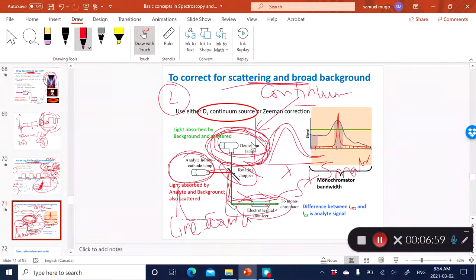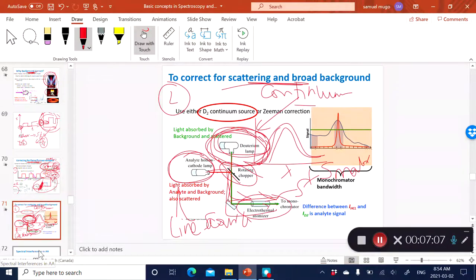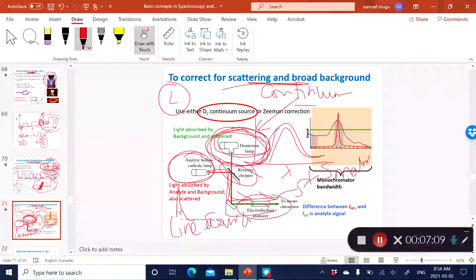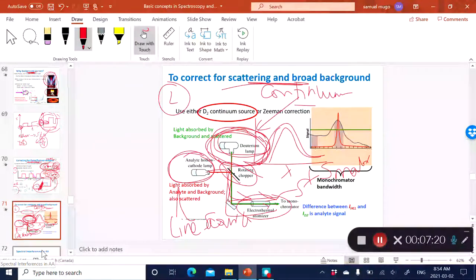This two-light-source approach is very common. You'll find lots of different instrumentation using background correction with one hollow cathode lamp and one continuum source, which largely detects the background coming from the matrices in the atomizer.